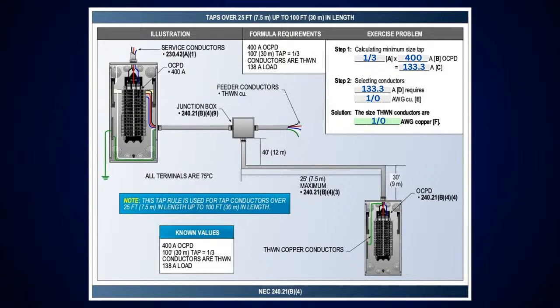In what case would I be permitted to tap a 10-foot section of, let's just say, number 14 gauge from a 150 amp main to, let's just say, a 15 amp receptacle? Would that be permitted, or would I have to have an overcurrent device? I don't know why you would do that. I've never seen that before. I'm just asking, would it be permitted, or would I have to go to a fuse? Well, usually when they're doing taps, they're coming off a good size overcurrent protection device and feeder upstream, and they're going down, setting another panelboard, or coming off a bus duct and going to gear or something. Usually you don't see it for things like that.